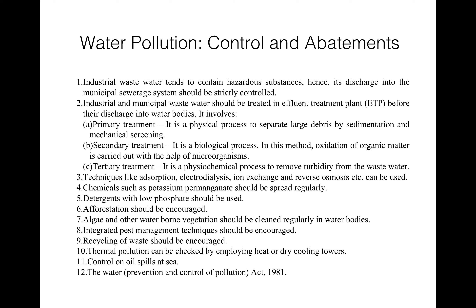Treatment involves three steps. First is primary treatment — it is a physical process by which large debris are separated by sedimentation and mechanical screening. Wastewater after screening is allowed to pass through a grit chamber where sand, grit and other solids settle. Then water is allowed to pass through a sedimentation tank or clarifier in which most of the suspended solids settle down due to gravity.